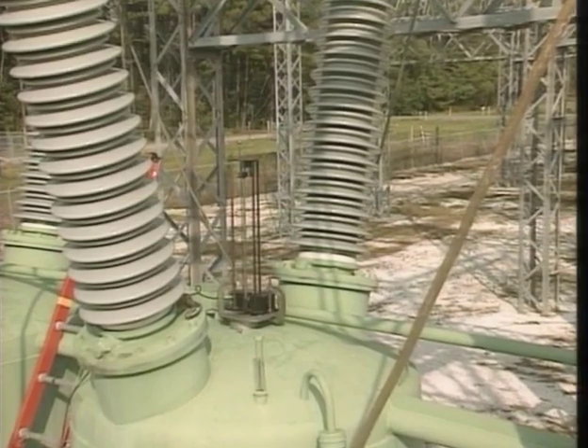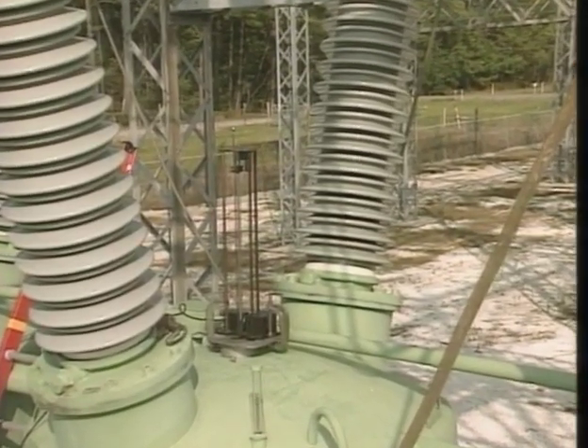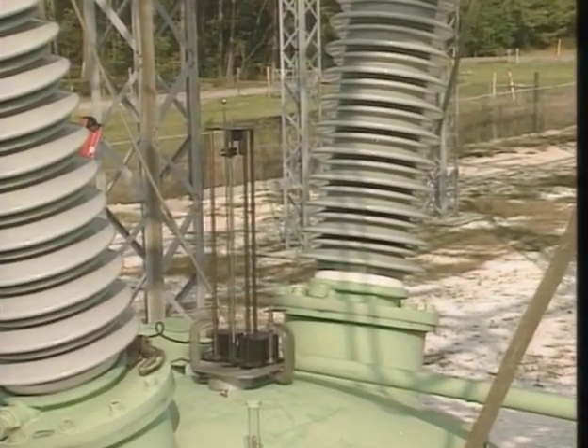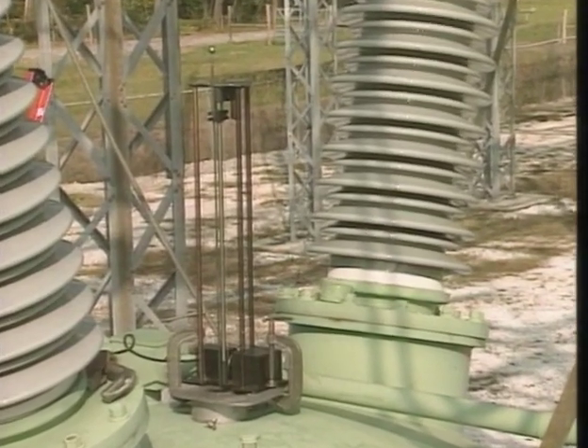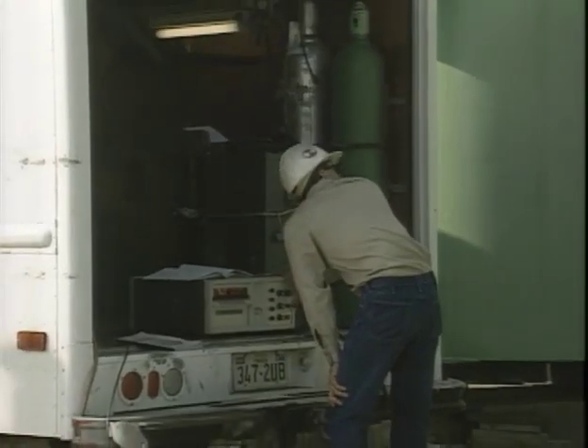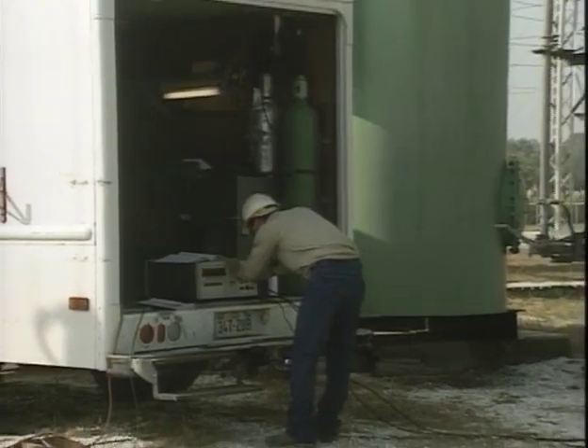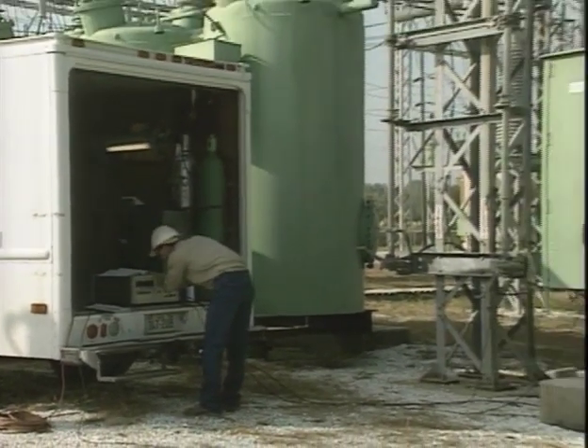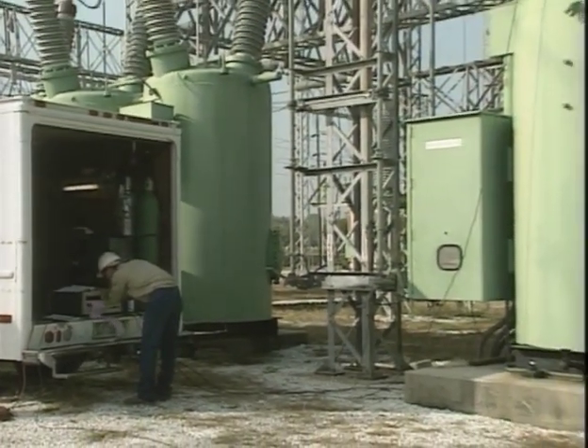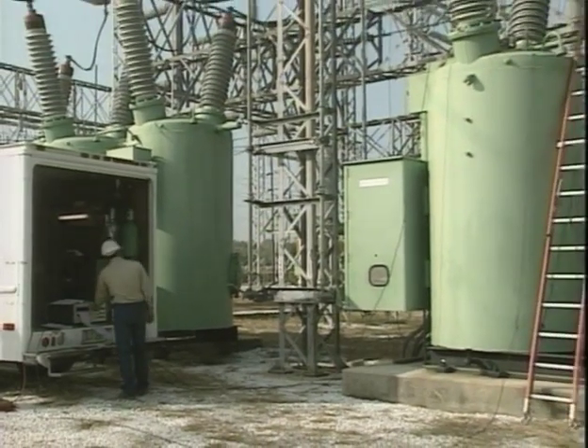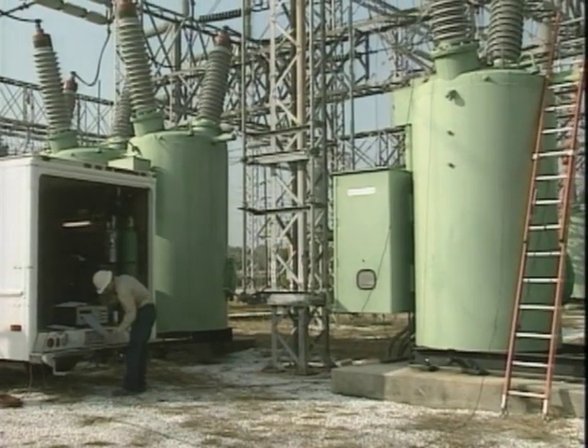One proof test that is usually recommended by breaker manufacturers is the time travel test. The purpose of a time travel test is to determine if the breaker can make and break circuits under normal load conditions, and if it can interrupt circuits under fault conditions. In principle, the test is performed by operating the breaker and measuring its electrical and mechanical performance. There are two main parts to the test: timing and travel.